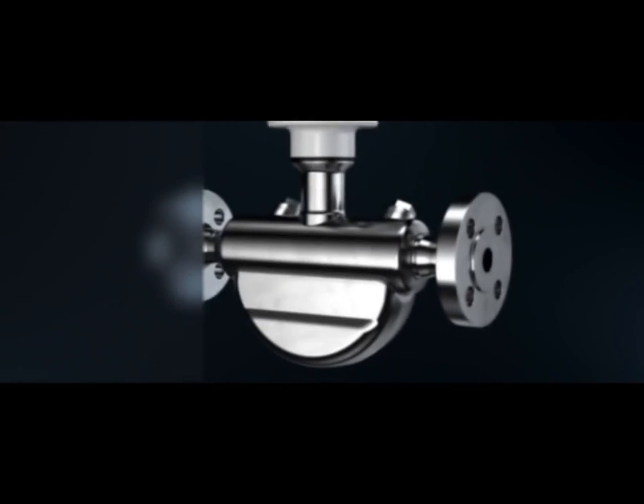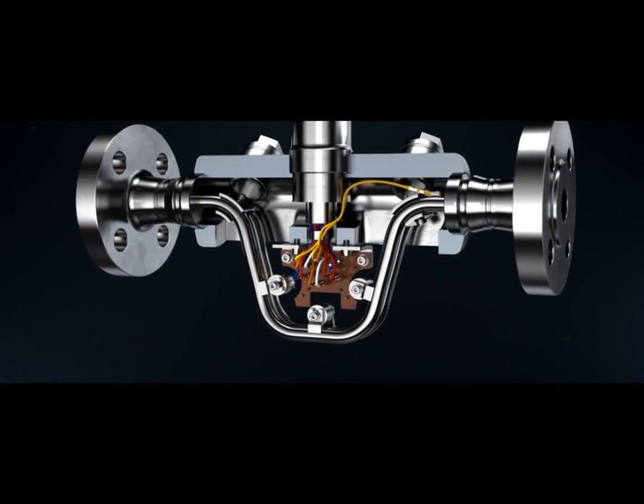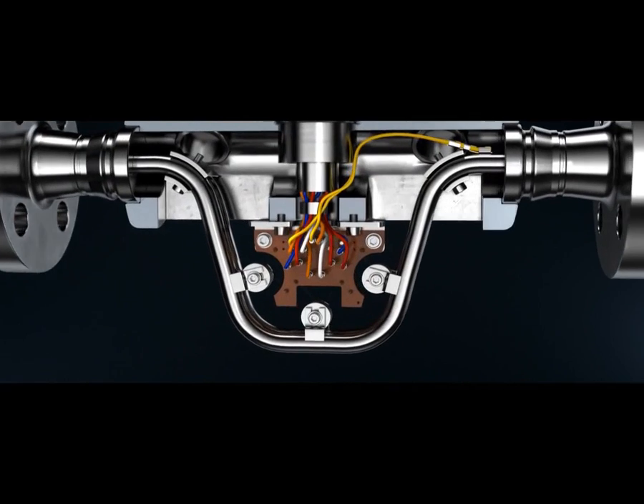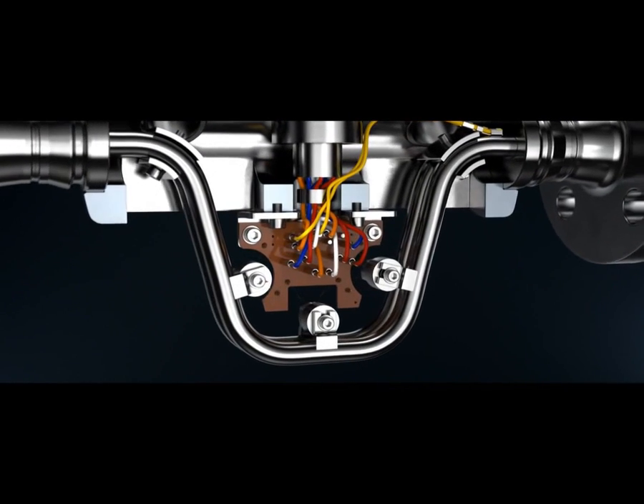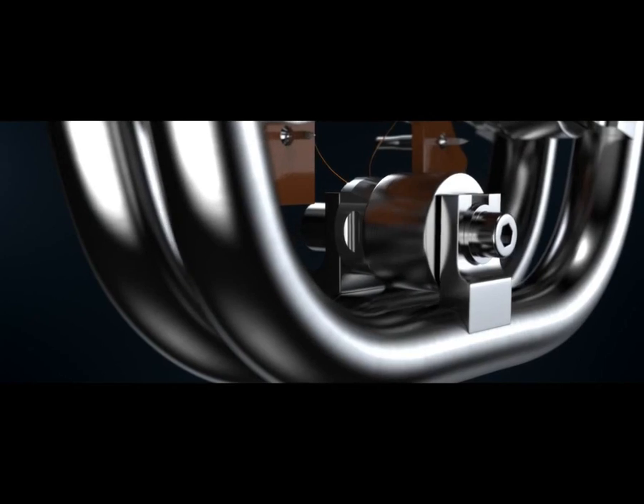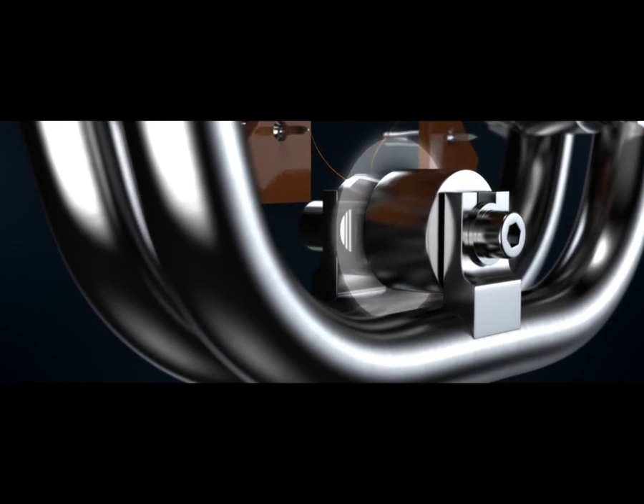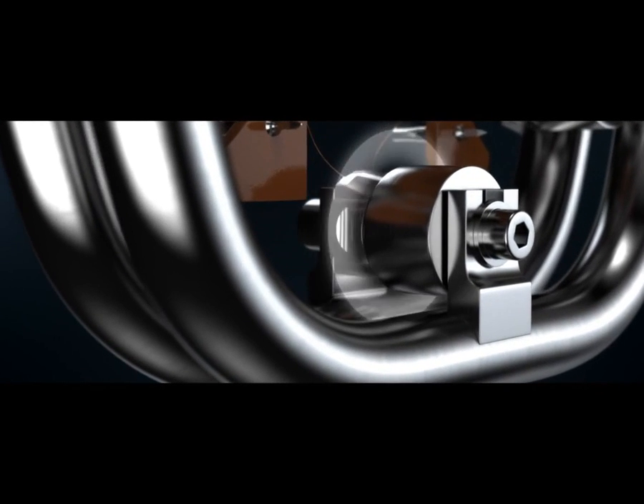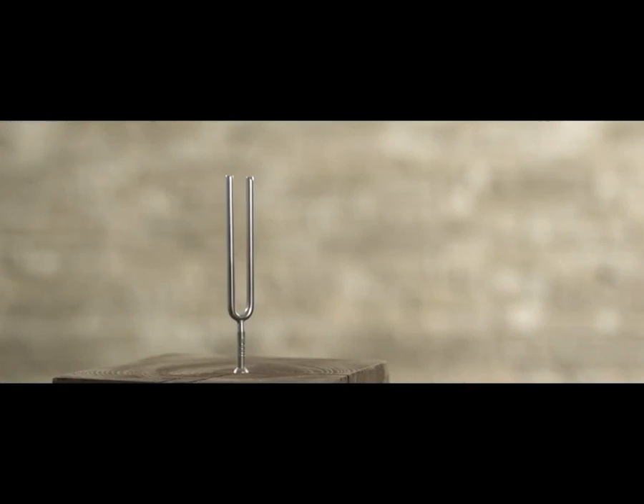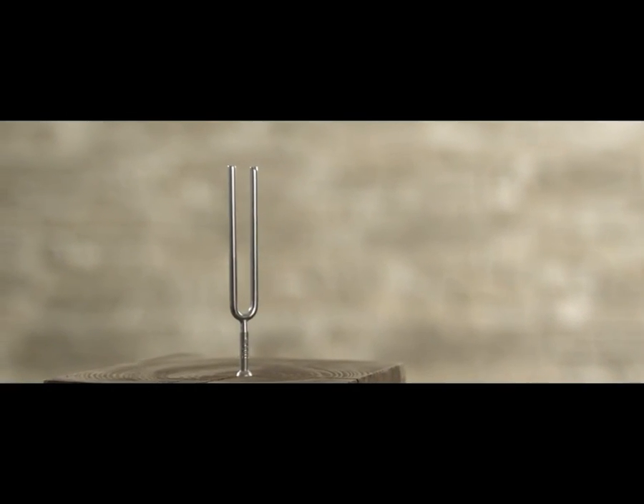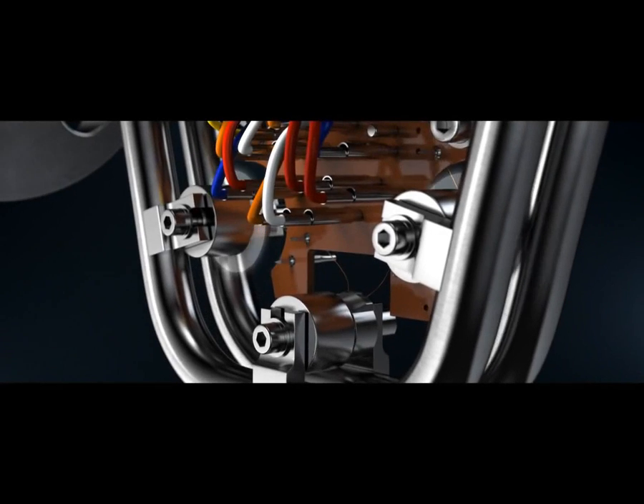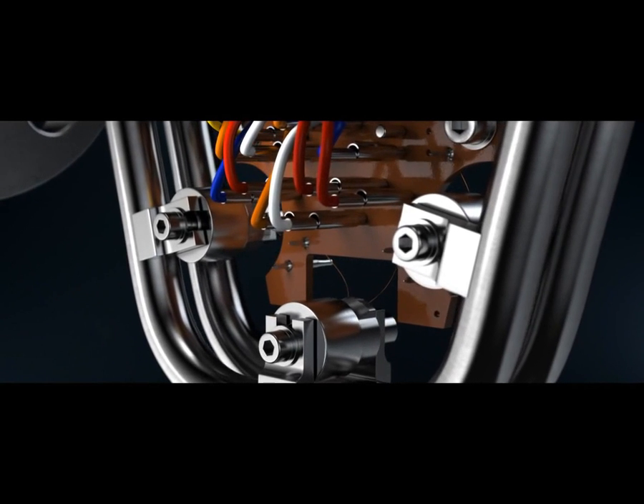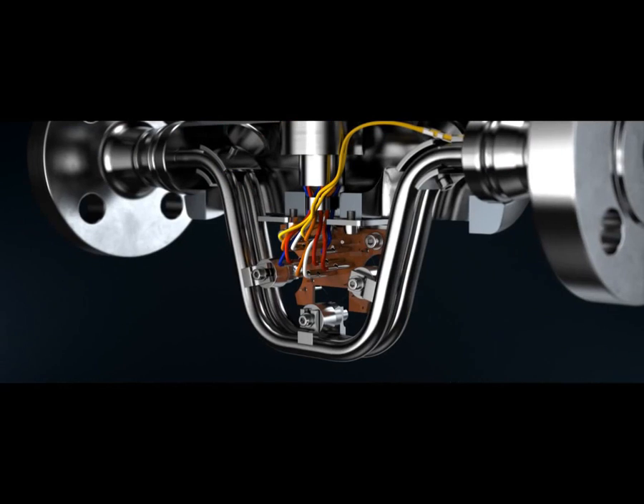The Siemens SITRANS FC430 flow meter functions according to the same principle. Two symmetric metal tubes are set vibrating. This is ensured by a driver coil in the central section. The tubes oscillate with a resonance frequency, similarly to a tuning fork. The oscillation is measured precisely by two pickups at the inlet and outlet sections.